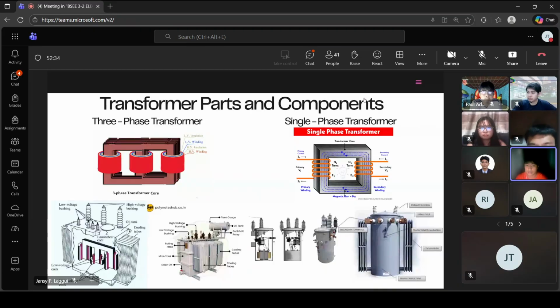Fourth is cooling system or cooling tubes. From the word itself, common sense naman siya - this part is to make sure na mape-prevent natin yung overheating. Fifth is conservator tank. It is a small tank placed on top of a transformer that holds extra insulating oil. So when a transformer gets hot, the oil expands and moves to the conservator tank, and when it cools down naman po, the oil goes back into the main tank. It's like a storage tank that lets the transformer's oil breathe, nakakatulong siya to keep our oil level steady and also to protect the transformer from damage na sanhi ng pagbabago-bago ng temperature.